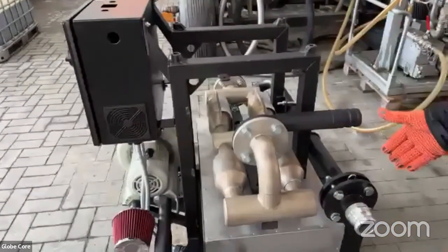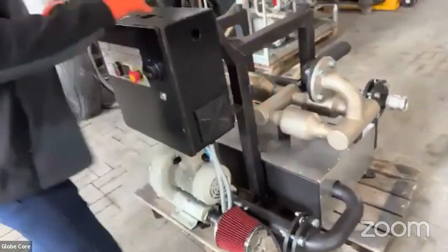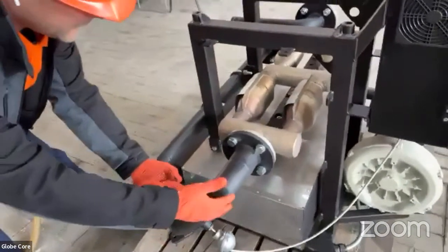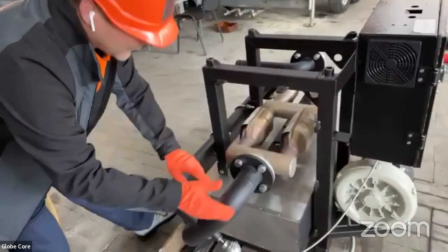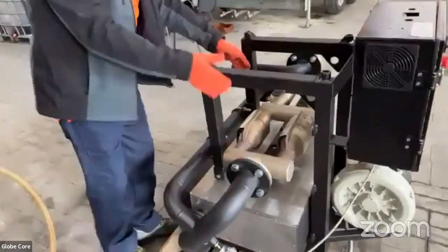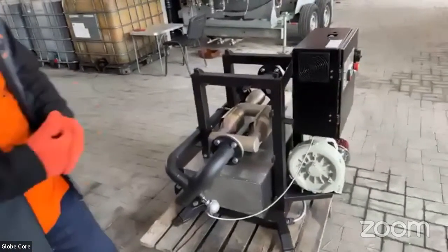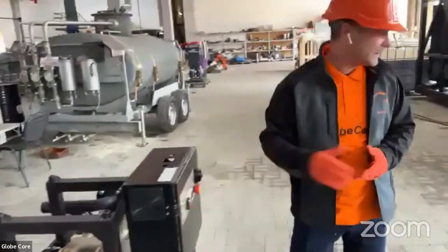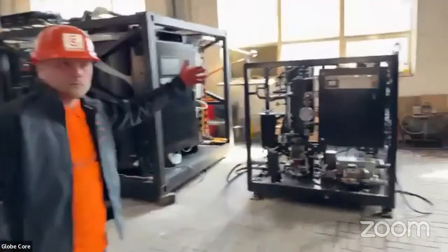So actually, it looks like this. We have an air blower. It supplies air into the heating area, and after that, it is mixed with combustion products from the regeneration unit, and then this mixture goes through the stages of catalytic converters. So in this way, we provide additional refining of the combustion products. As I told you, this unit can be supplied separately and be used in combination, let's say, with this machine.